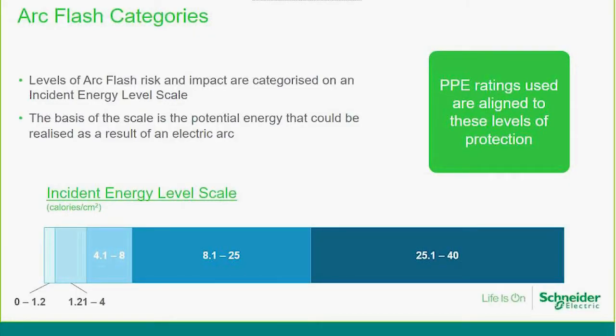We categorize it by the incident energy level scale. So as I mentioned before, it's a measure of the energy that's likely to be present for a given period of time at that point in the network that you're working. As you can see, there are very low levels of incident energy, 0 to 1.2, and they go up in magnitude to 25.1 to 40 cals per square centimetre. Now that doesn't sound a lot, but what you need to do is understand what levels of PPE are required at those levels. So I'm going to make things very clear. This is a function of current and time.